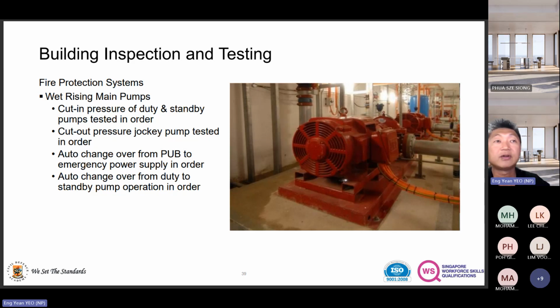All right, so every building is different, because they need to look at the most remote location to hit the minimum pressure, so that at the sprinkler head that spray pattern can be created. And that's why there is this overlapping of spray patterns at the end of the system itself. They will not test every single location. What they do is get the most remote one to test it. Once the most remote point, meaning the highest point from the sprinkler pump room, will be deemed the weakest point, in the sense that the pressure will be the lowest. But that lowest pressure will need to hit the minimum pressure that we want. If not, then you will not be effective. All right. Okay.